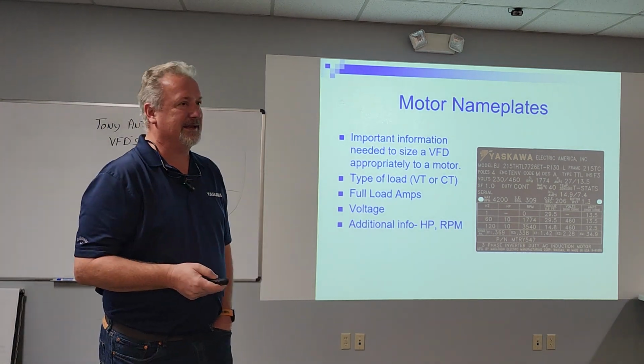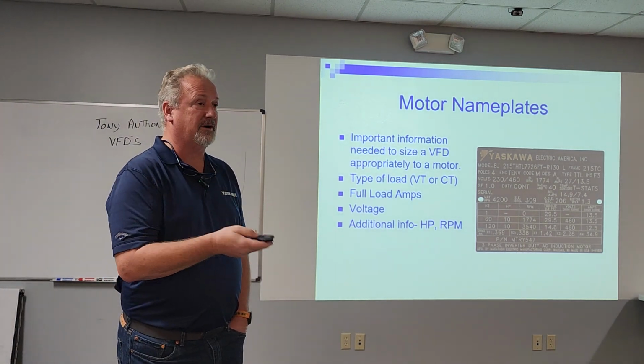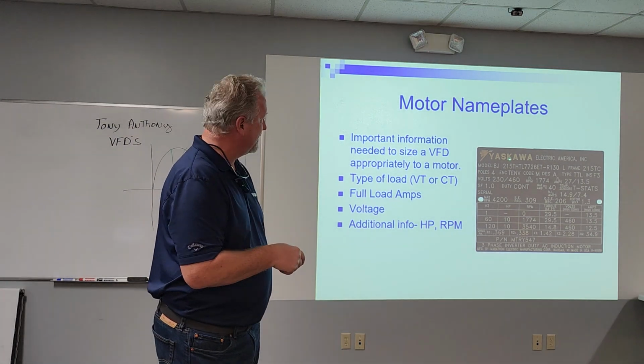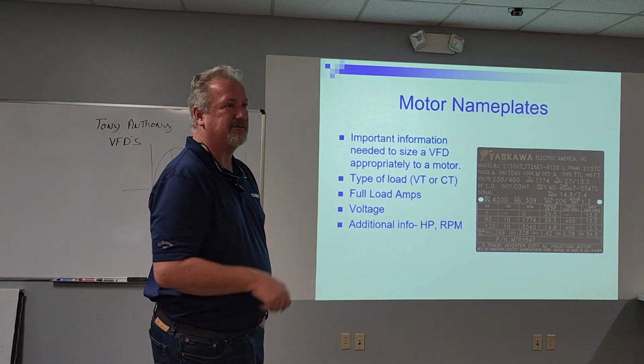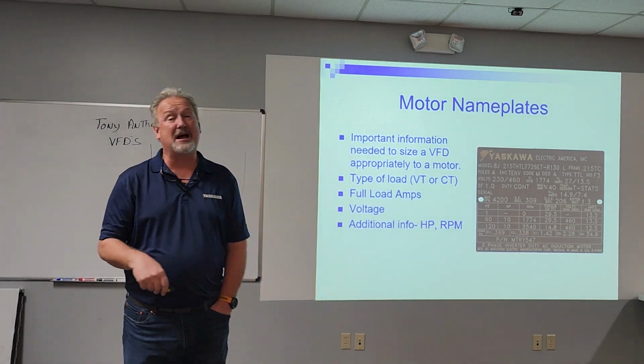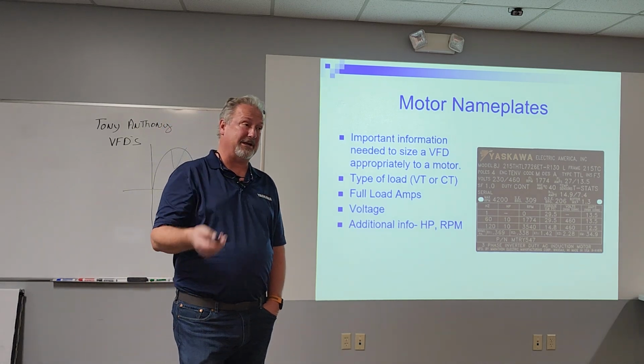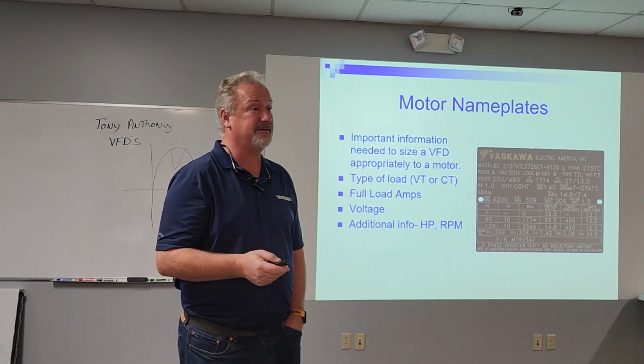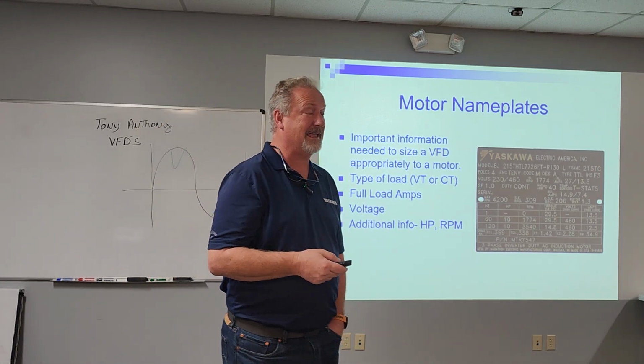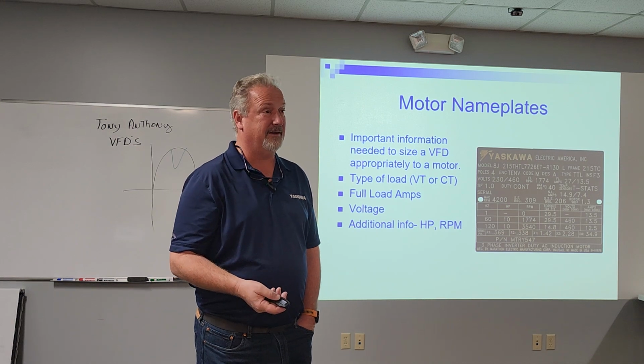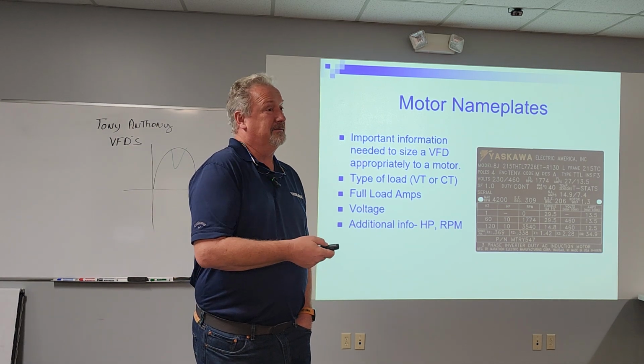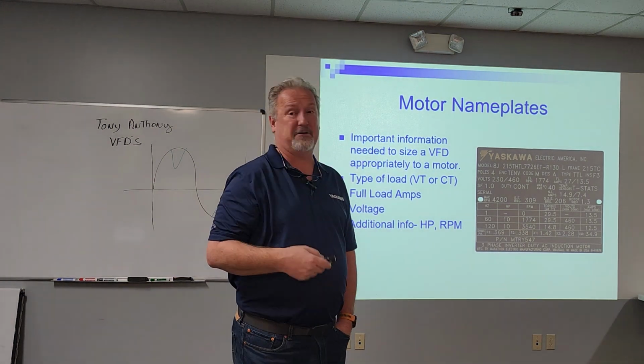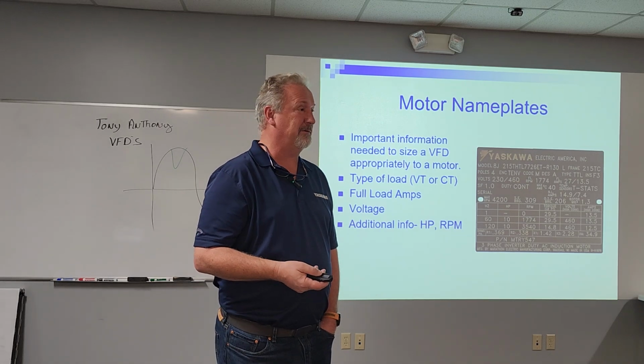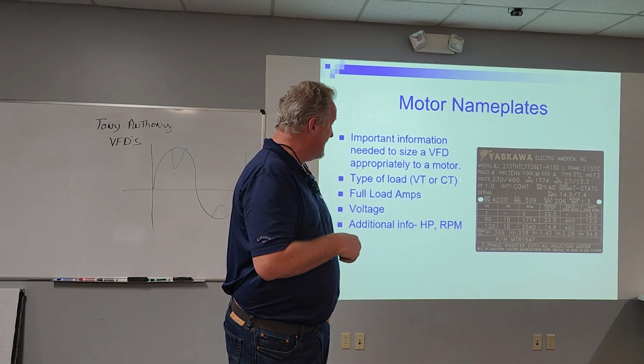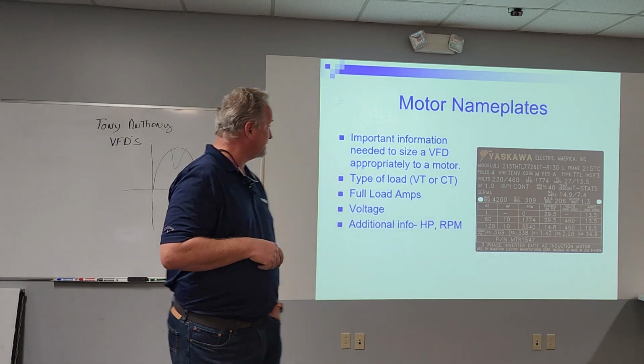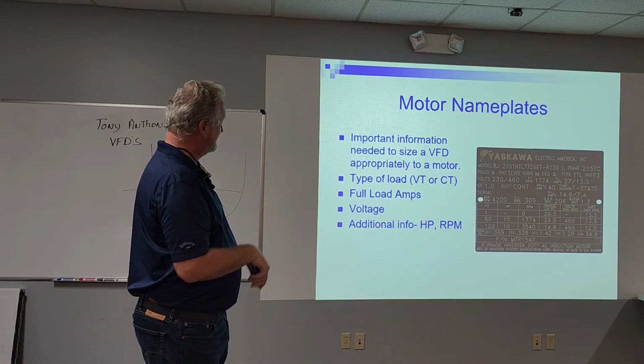That is the biggest thing. We need to know the voltage, because most motors out there have a 230/460 rating, they are dual rated. Drives are not. What we put in is what we get out. And you'd be surprised how often that still happens. Somebody calls and says, hey, I let the smoke out of this drive. I put a 230 drive on a 460 load and it blew up, because they didn't realize the drives are not dual rated. Oh, actually, this says it right here.